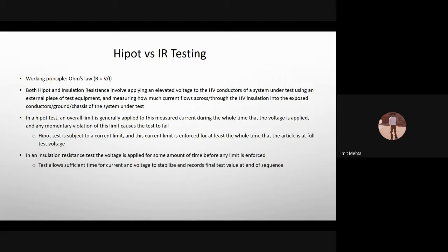HiPot and insulation resistance testing basically involve applying a high voltage to the conductors or device under test. An external unit measures how much current is flowing between the tester and the component being tested, and from that it calculates the resistance and decides, based on your specification limits, whether the article is acceptable or not.